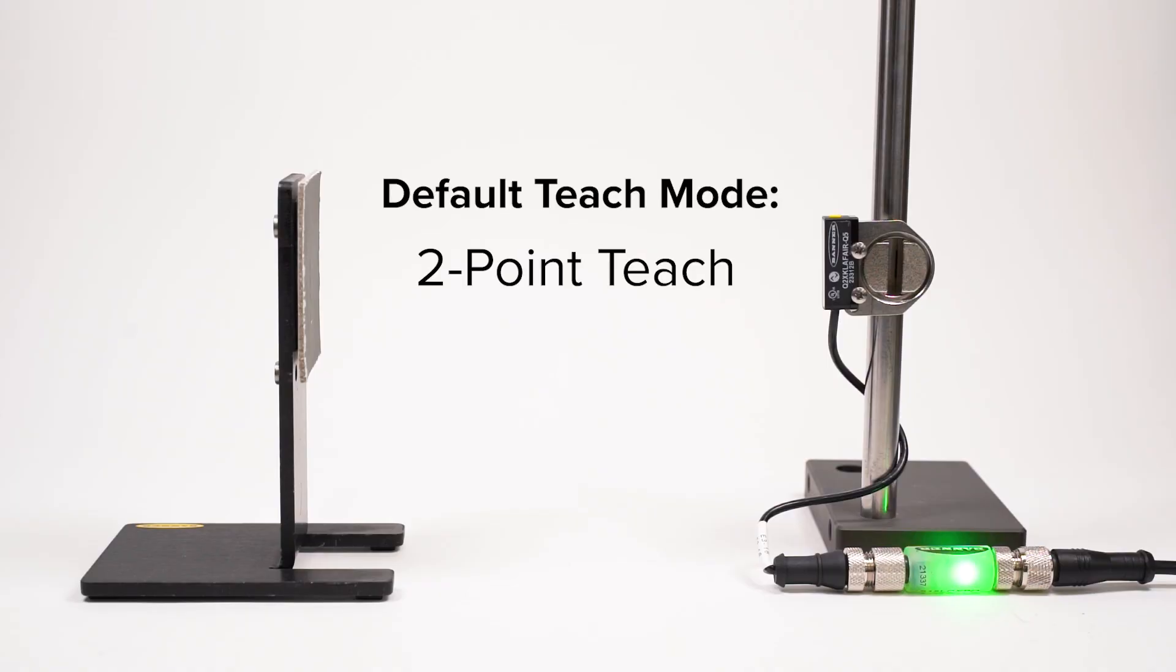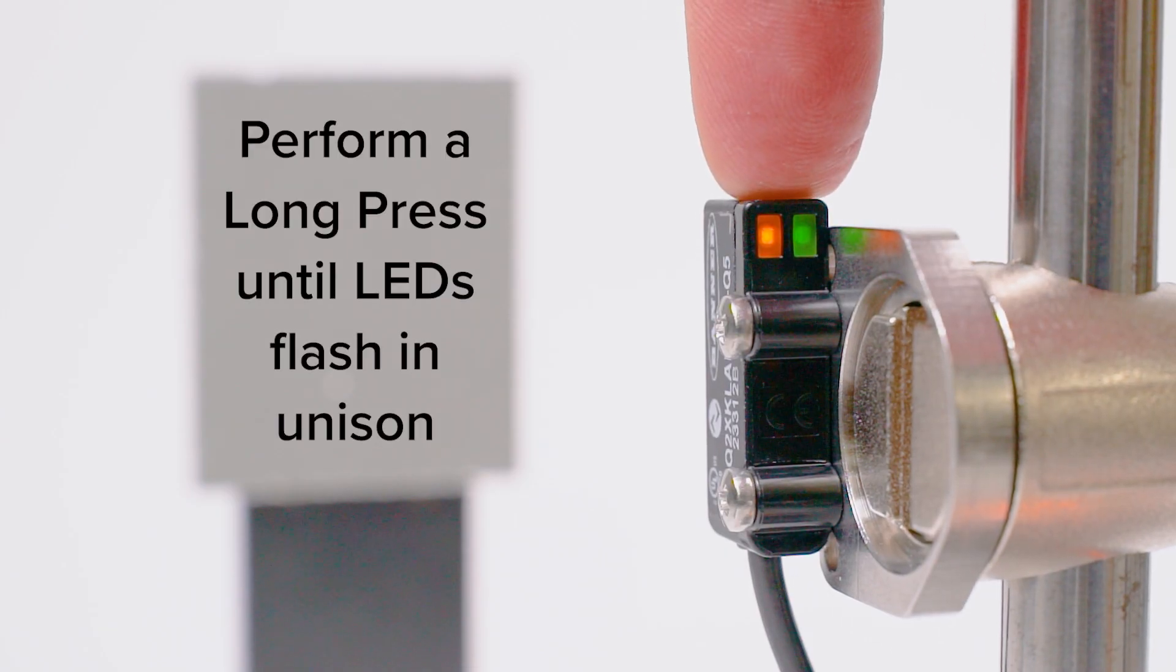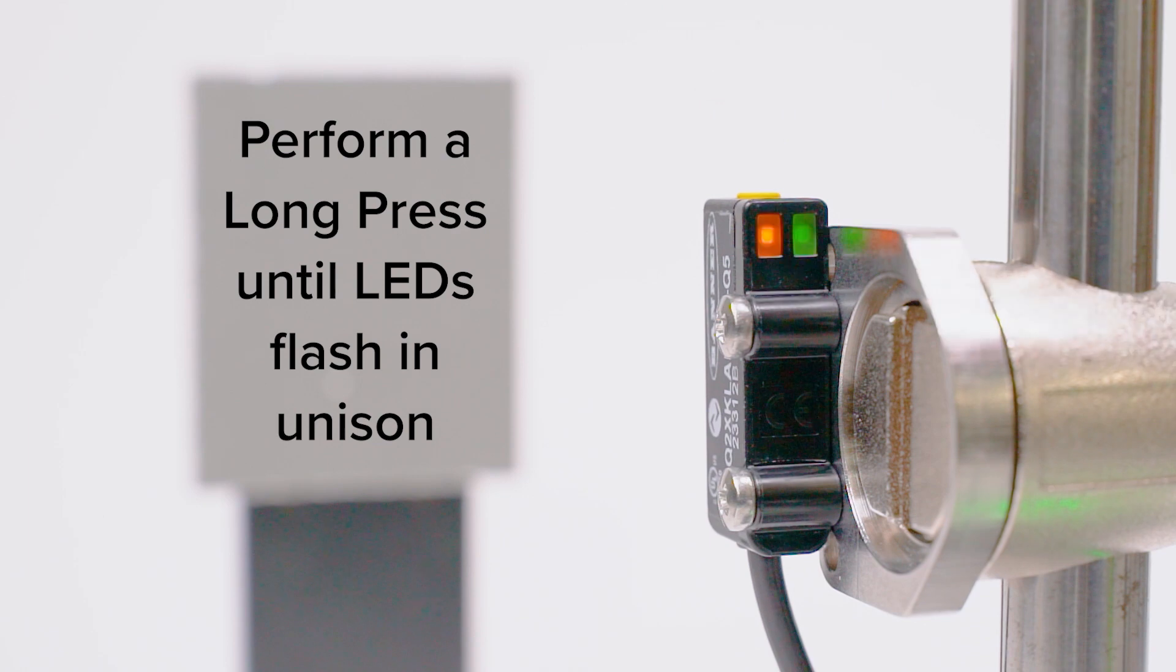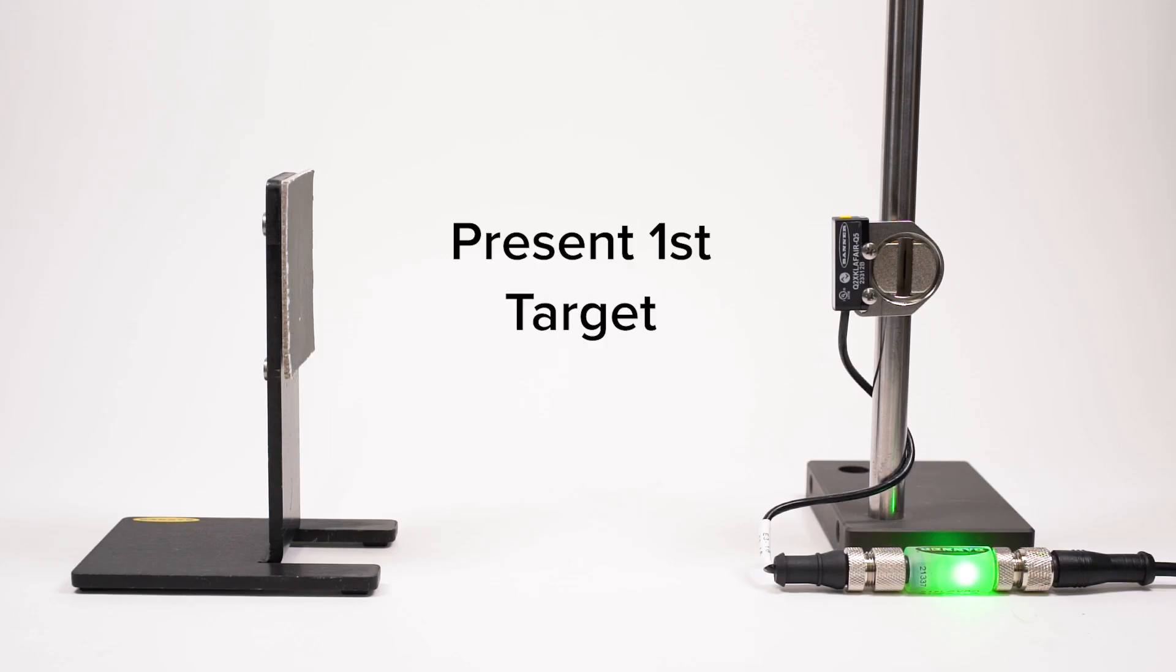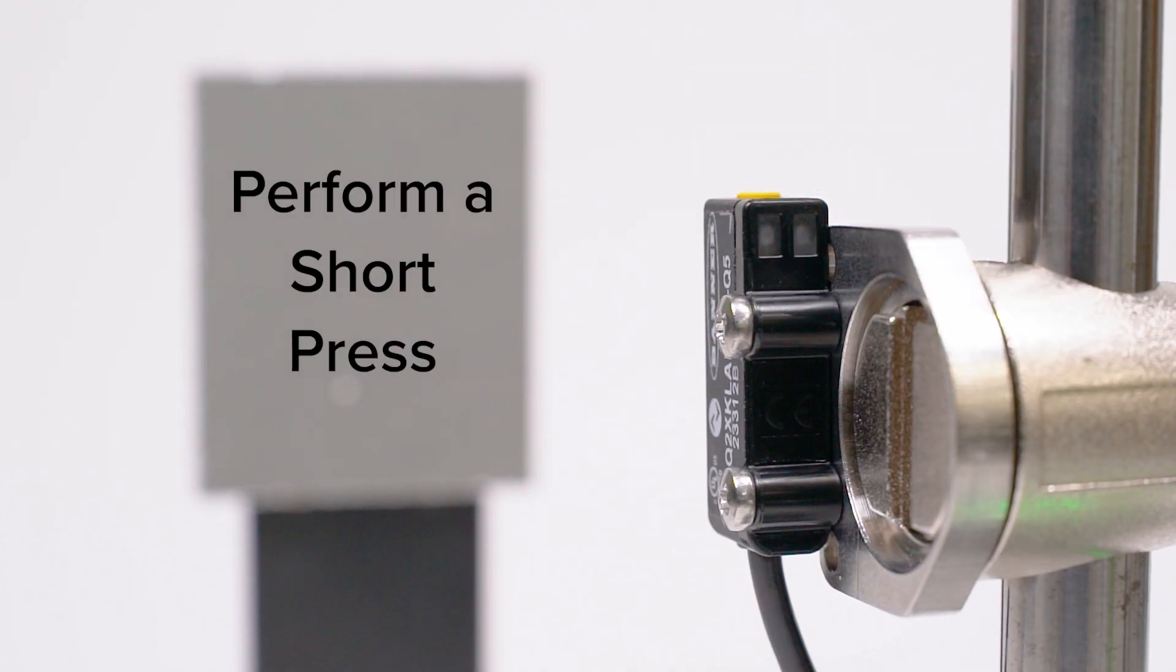The default teach mode is two-point teach. To initiate the teach process, perform a long press of the button until the LEDs flash in unison. Present the first target or distance and perform a short press to set that first condition.